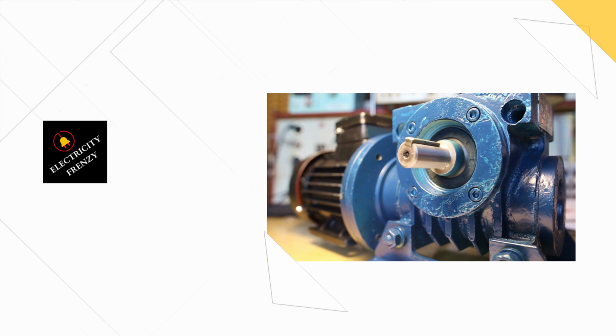Additionally, if the motor is running at a slower speed than intended, adjustments should be made to ensure it operates at the correct RPM. Regular maintenance and inspection of the motor's cooling system can help identify and resolve cooling-related issues early on. This includes checking the fan, cleaning the ventilation openings, and monitoring the motor's RPM to ensure it is operating within the recommended range.